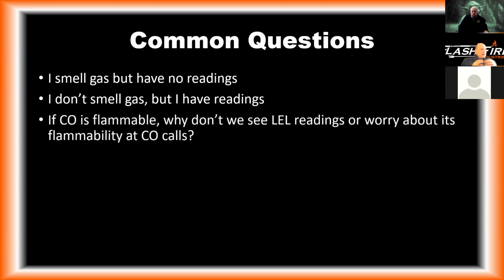So if CO is flammable, it has a flammability and it's labeled as a flammable gas. If it has a flammability range of about 12.5 to 74%, why are we not seeing LEL readings? And why, when we go to a CO alarm, are we not concerned about the flammability of CO? It's a very good question. We have to remember, and we'll throw some math in here, 12.5% in air is 125,000 parts per million. So our lower explosive level of CO is 125,000 parts per million. Remember, our IDLH is 1,200 parts per million. So CO is going to kill you well before it becomes flammable.